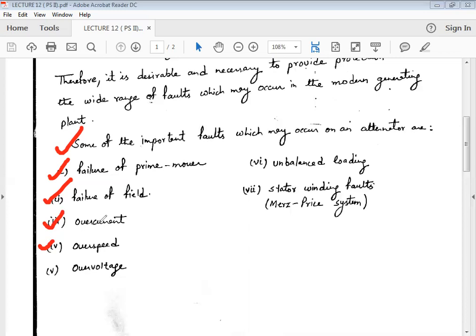Overspeed mostly occurs due to the sudden fall of load. When we talk regarding overvoltage, it occurs due to insulation failure or if we suddenly cut off the load. In the case of steam turbines, we use governors. Governors can easily control the main valve, which is the input to the turbine, so that the speed of the turbine gets controlled. Alternatively, we can use overspeed relays for this particular purpose.